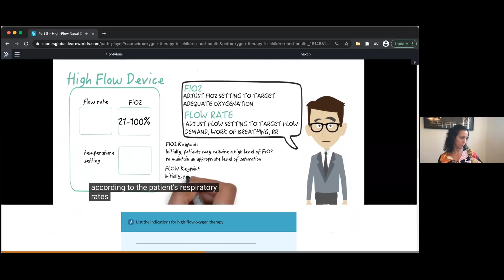So I think we should just stop the video for a second here because this is a really good point to make, that the flow rate on the high flow oxygen therapy devices can be set up to 40 liters per minute on some devices and up to 60 liters on other devices. And when we are breathing at rest, we are breathing 20 to 30 liters per minute. But when we have respiratory distress, that flow increases significantly. So as providers, when you're setting the flow rate on your high flow oxygen therapy device, you really need to evaluate your patient's respiratory rate.